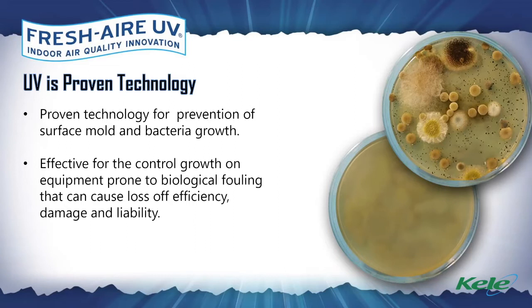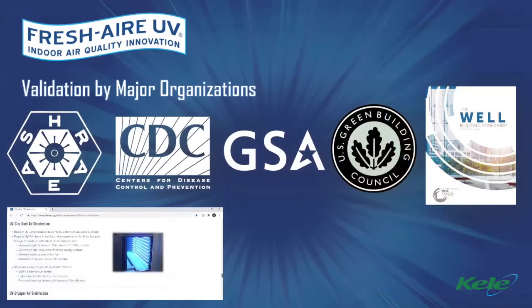Studies have shown that the condition of our air quality is severely impacted by the condition of the HVAC system. So if there's one thing that I would wish that you leave here today, of course, SARS-CoV-2 is top of mind, no doubt about that. But the condition of our HVAC equipment is imperative. And the condition of that HVAC equipment is directly correlated to how we feel inside of our homes or inside of our buildings. So please, moving forward, do not lose sight of the coil. Do not lose sight of the drain pan. This is definitely a most strategic location for any UV system to address those microbial contaminants that are growing inside the dark, cool confines of the air handling unit.